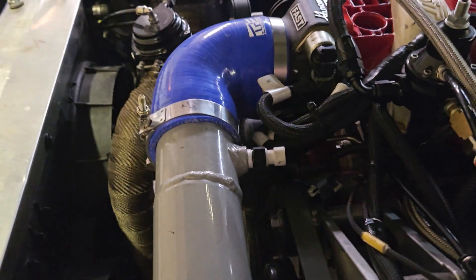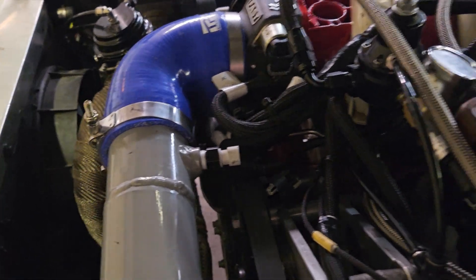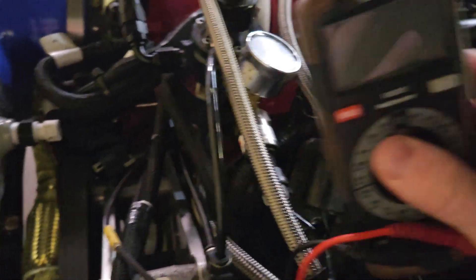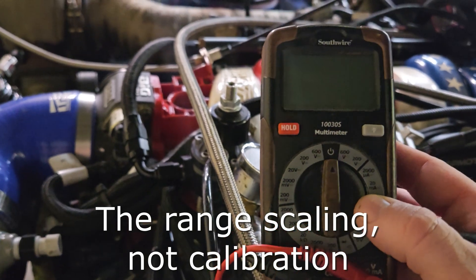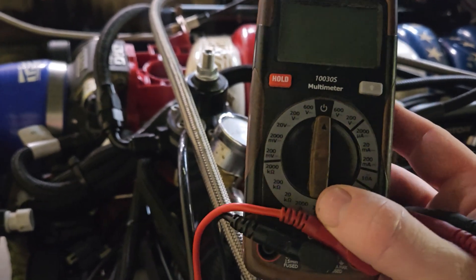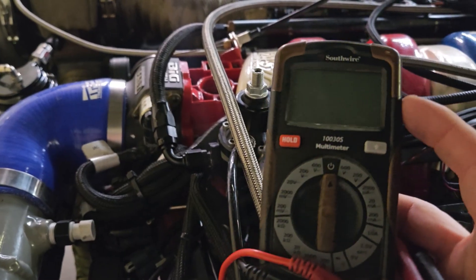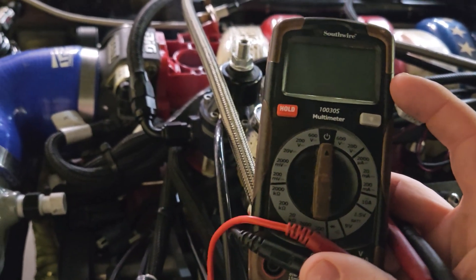If the sensors are reading off and you're looking for assistance, the first thing we'd have you do is troubleshoot. You would pop off the connector at the back of the sensor if you can reach it and back-probe it. Compare your reading on your multimeter, which would be set to the ohm scale. Make sure if you have one that will auto-range, pay attention to what range it's on. I had a customer say they had single-digit readings and it turned out it was in the kilo-ohm scale — easy thing to miss. Instead of reading 7 ohms it was reading 7.2 — actually 7,200 ohms. Big difference.